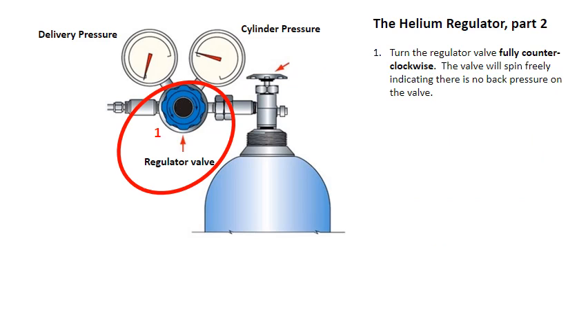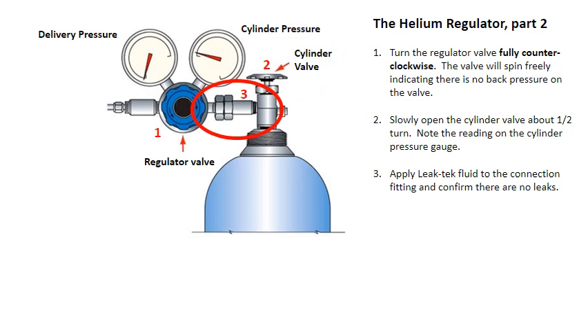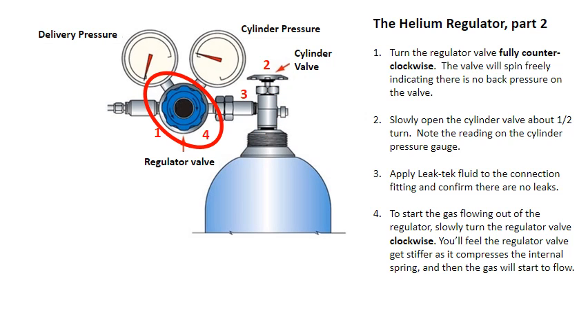Turn the regulator valve fully counterclockwise — the valve will spin freely, indicating there is no back pressure on the valve. Slowly open the cylinder valve about one half turn. Note the reading on the cylinder pressure gauge. Apply Leak-tek fluid to the connection fitting and confirm there are no leaks. To start the gas flowing out of the regulator, slowly turn the regulator valve clockwise. You'll feel the regulator valve get stiffer as it compresses the internal spring, and then the gas will start to flow.